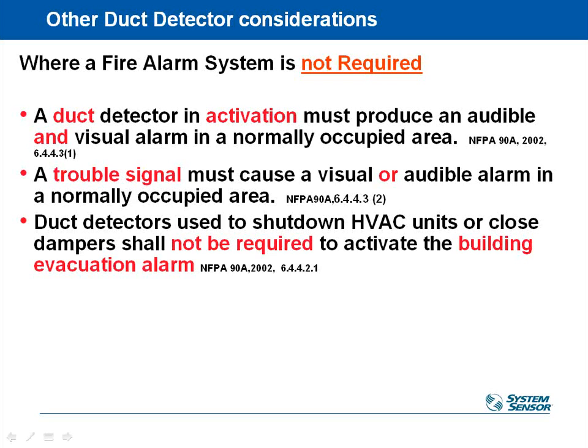All right, so if you don't have the requirement for a fire alarm system in your building, but you still have to put a duct detector in because it's more than 2,000 CFM, you may be required to have an audible and visual alarm in the actual space. Doesn't mean you have to have it in every single space, and doesn't mean you have to have all the pull stations and all that stuff. You don't have to have a full fire alarm system, but you have to have something in the space that makes a visual indication like a strobe light and an audible indication like a horn to let people know in that space that there is an issue.